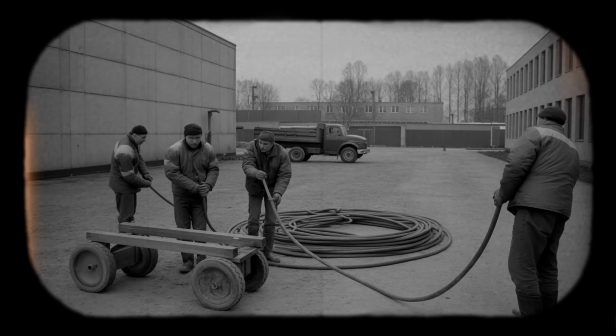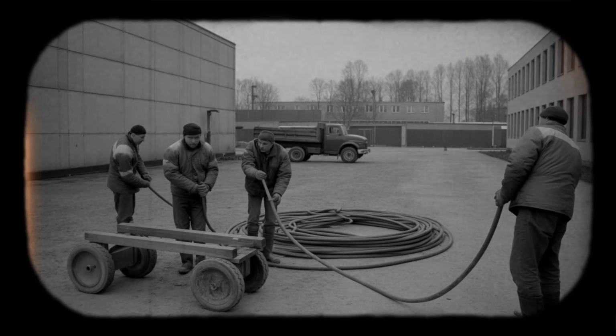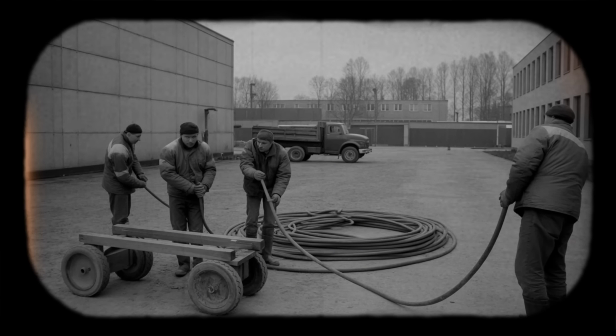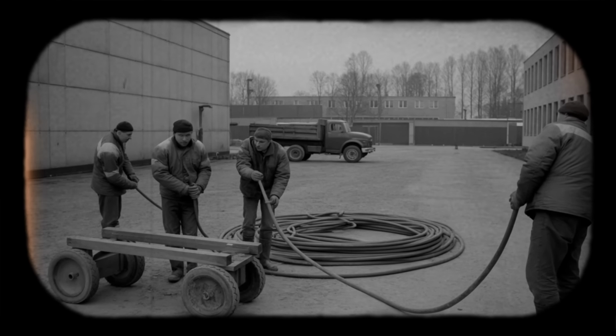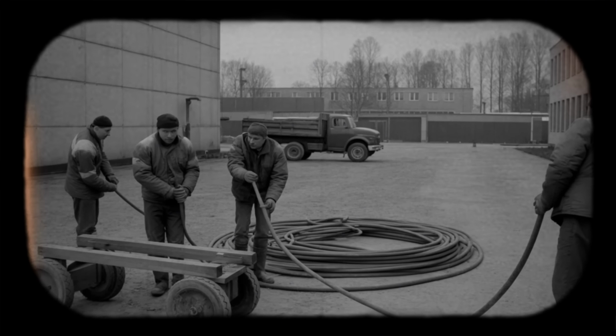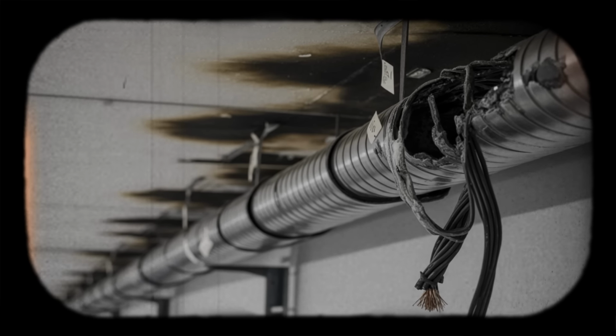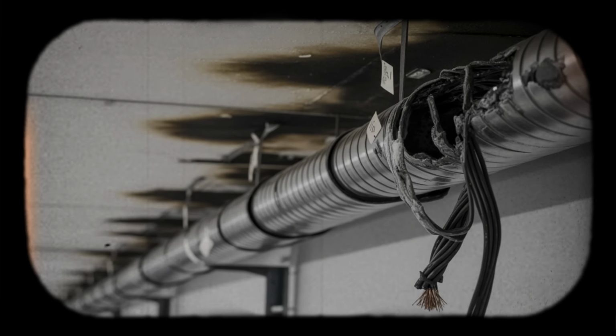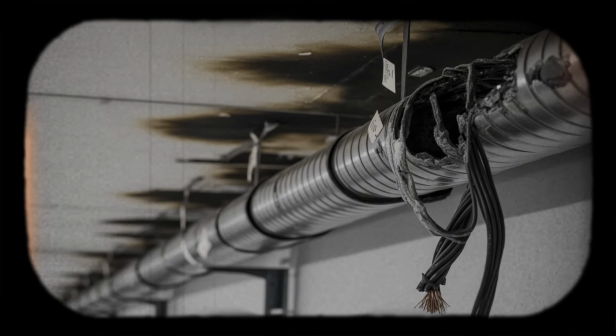At 11:08, the control room log recorded a cable fire alarm in or near the 6 kV switchgear feeding standby power. What happened in the switchgear room would take years to fully reconstruct. An electrician performing work on the standby transformer made an error. Exact details remain sparse in open literature, but the effect was immediate and severe. A three-phase short circuit developed, and high short-circuit current began flowing through the 6 kV cable.